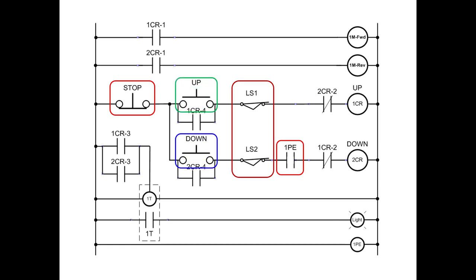Now the up and the down button are going to control the motor. That's a single motor. I show it as two circles. In reality, it could be one circle with three leads, a common, a forward and a reverse. And actually, if this were an industrial garage door, those could be motor starters. A reversing motor starter has two and if it's three phase, one of the phases is reversed on one contactor, then the other and that's how you get your forward and reverse.